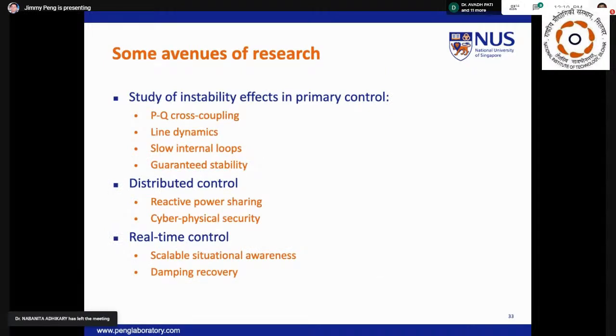Now, the stability problem of power sharing among inverters in a microgrid can be addressed by first studying the properties of instability in the primary control. Contributing factors include cross-coupling effects, line dynamics, internal loops of inverter, and stability margins. Now, primary controls are typically executed using distributed control, where the challenges of reactive power sharing and cybersecurity need to be addressed. Real-time control plays a critical role in ensuring the microgrid can recover from disturbances via near real-time situational awareness of the stability issues at hand.